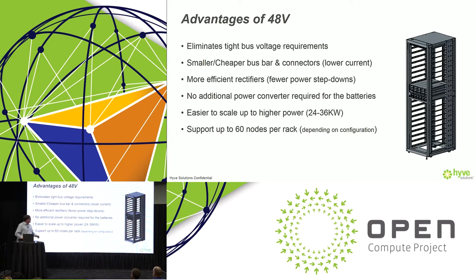The rack can go up to 60 nodes per rack, but as always the proof is in the configuration. The rack is a 42 OU rack — a very traditional form factor. When you allocate 3 OU for the power shelf, 3 OU for the battery backup unit, and a few OU for switching gear, you've got about 30 to 34 OU left for IT gear. GPU-based units will use higher power density per OU, but the overall message is that the 48-volt open rack scales to higher power density than lower-voltage configurations or traditional racks without in-rack power distribution.